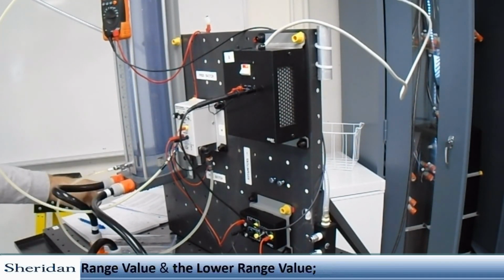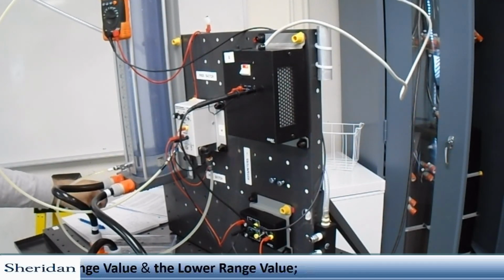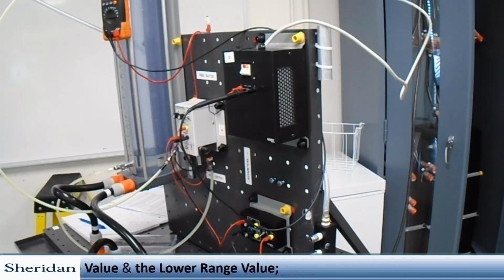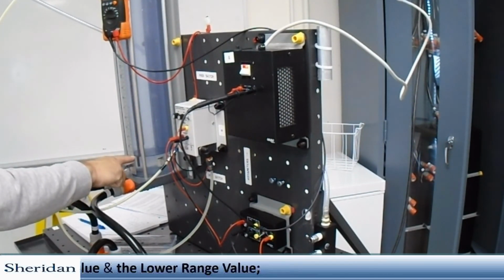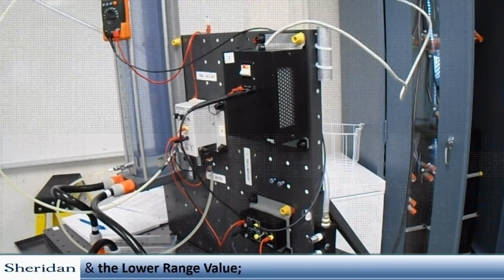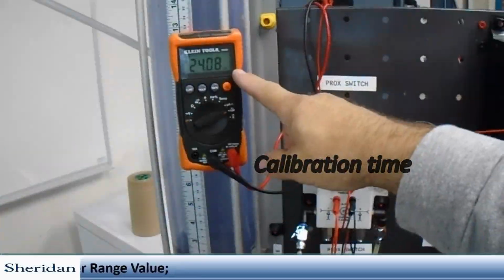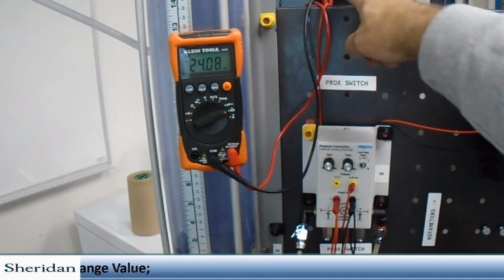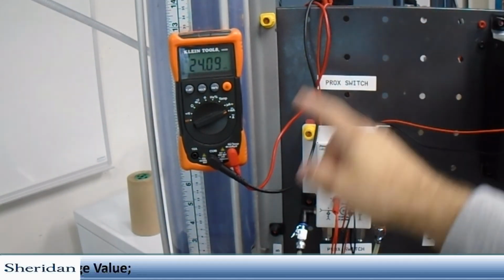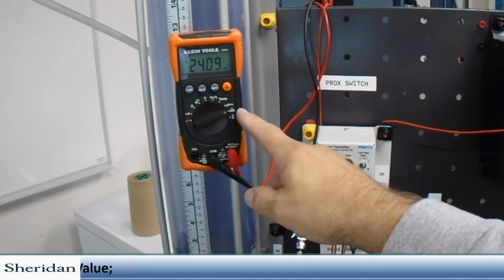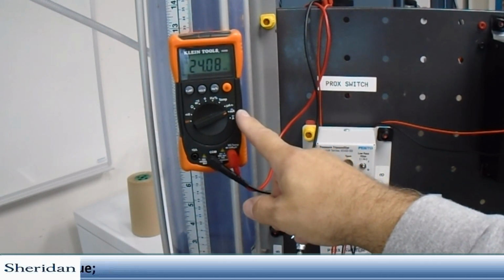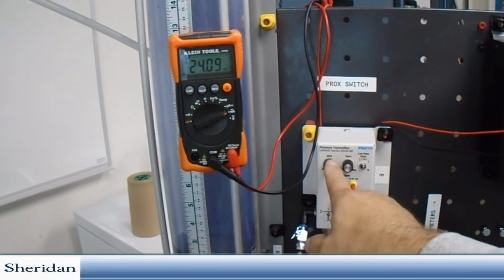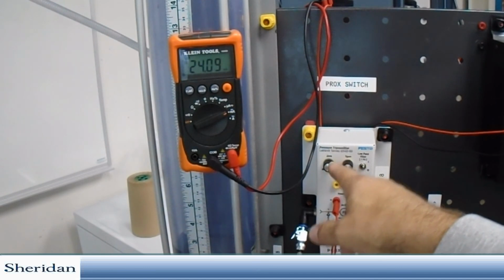In this particular case, there may be a small bit of leakage from the actual fittings. For the most part, we are at 2 inches. Now we can begin our calibration. So we have an amp meter in series with a 250 ohm resistor, and we're going to use it to determine our current output. So right now we've set our zero up to maximum, which is way beyond what we want.